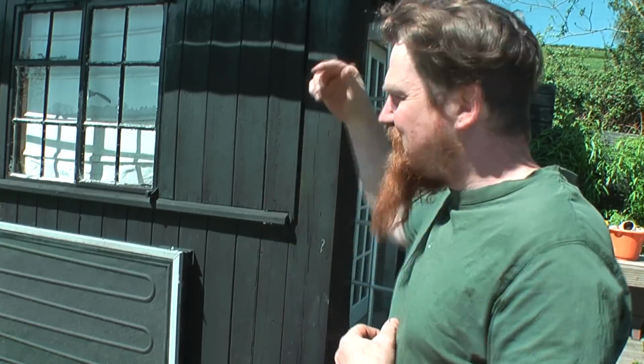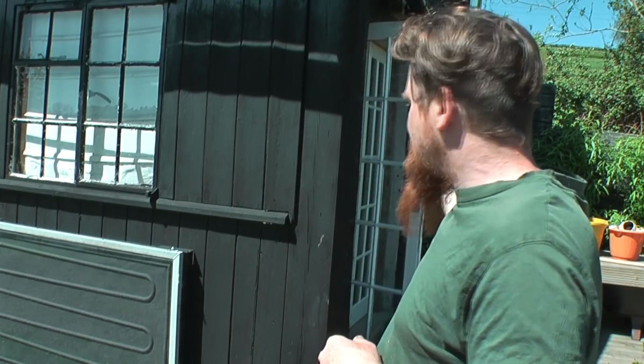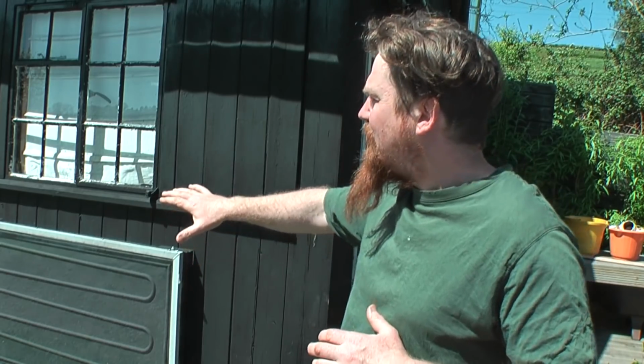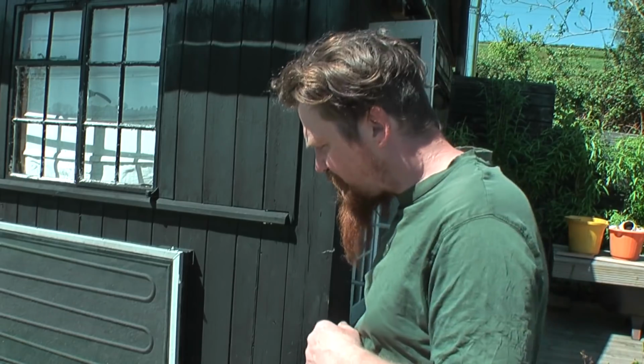What I've had to do with the panels is almost shut them off, because the thermosyphon, despite the skepticism, the thermosyphon system is too efficient at removing the heat from the panels. What I've done is almost shut off the ball valve on the return line, and that's slowing the flow enough for the panels to get up to some proper hot temperatures before that heat migrates up into the heat exchanger. So we'll see how much more is to come.